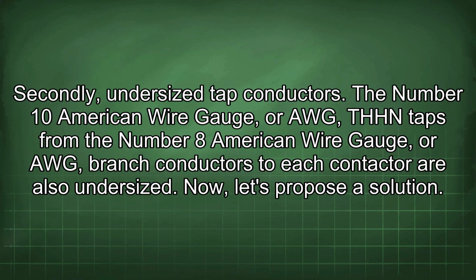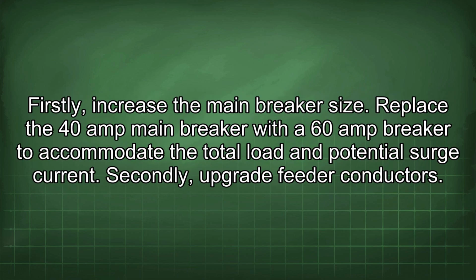Secondly, undersized tap conductors. The number 10 AWG THHN taps from the number 8 AWG branch conductors to each contactor are also undersized. Now, let's propose a solution. Firstly, increase the main breaker size. Replace the 40 amp main breaker with a 60 amp breaker to accommodate the total load and potential surge current.